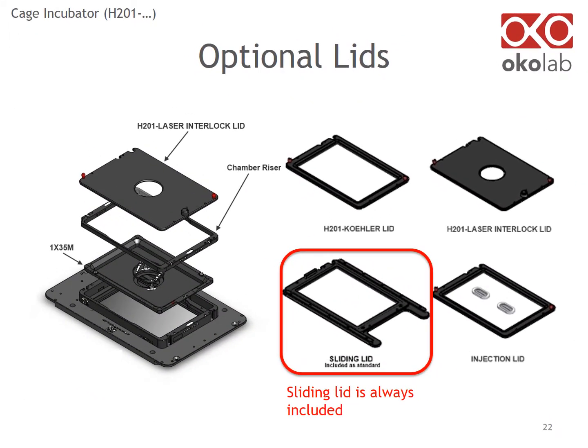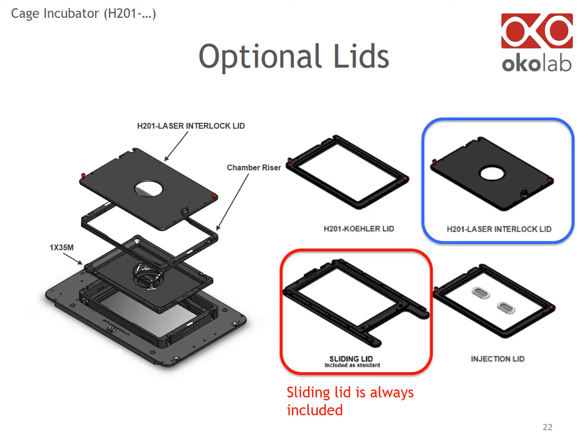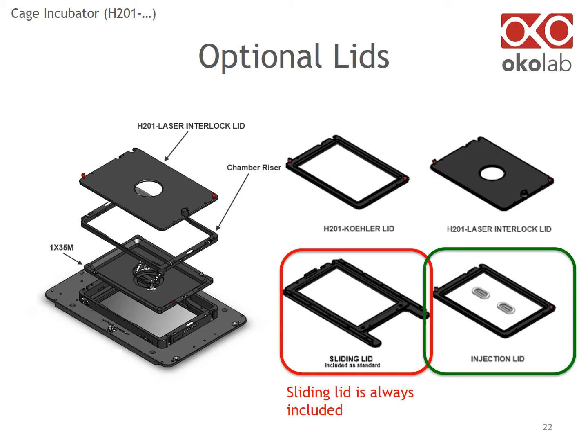This slide shows optional lids available for the most common chambers. The sliding lid is always included. The Koehler lid allows you to focus the condenser in case your condenser has a short working distance. The laser interlock lid adds safety when using laser applications, and the injection lid is for the insertion of needles or capillaries. Note that the laser interlock lid and the injection lid are compatible only with an insert for a single 35mm dish.